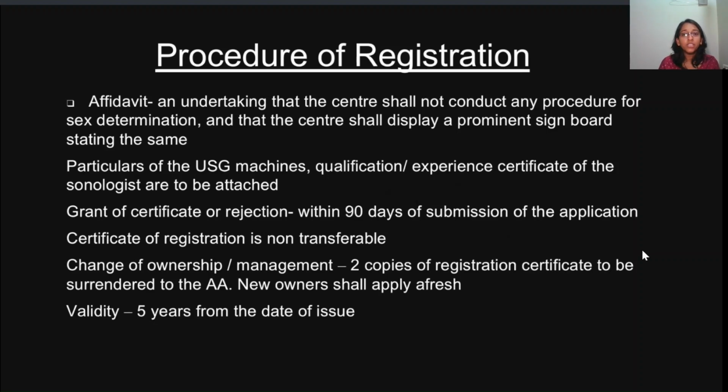And the certificate of this approval registration is non-transferable. You can't register a certain ultrasound machine in your clinic, and once you shift the machine to a different clinic, you can't transfer that certificate there. They have to register it again under their place, their name, and that machine has to be re-registered. And for re-registration also, it's Form A. And we're coming to that.